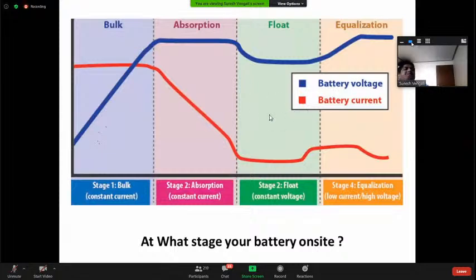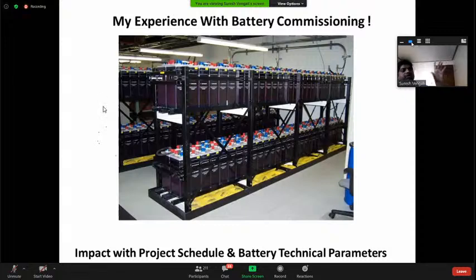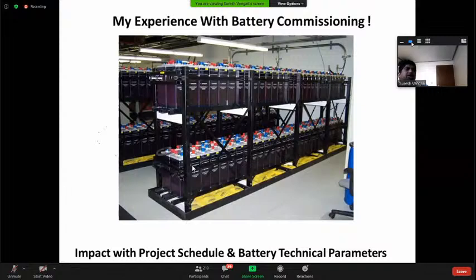You can view these 4 cycles from your battery monitoring system through the healthiness data. The advantage you get is related to man-hours, whether you call a vendor to commission the job or do it yourself. If you don't verify properly, it impacts the project schedule and man-hour schedule. So the battery monitoring system is a very crucial item to check healthiness and control cost, and this additional equipment cost can be justified by that.